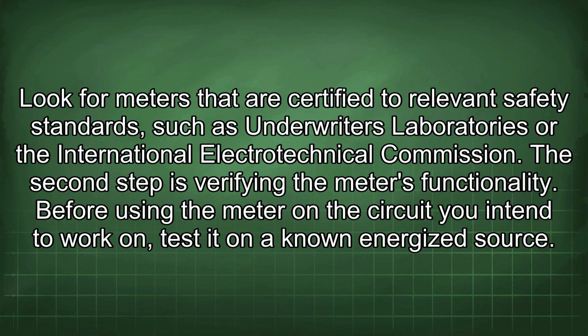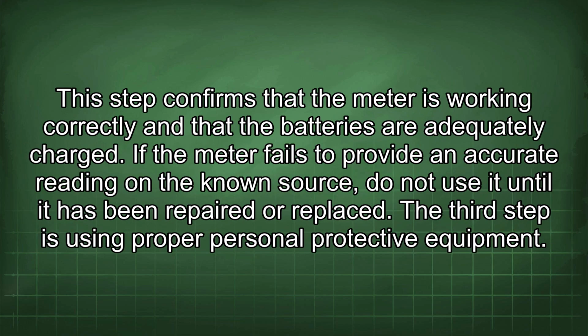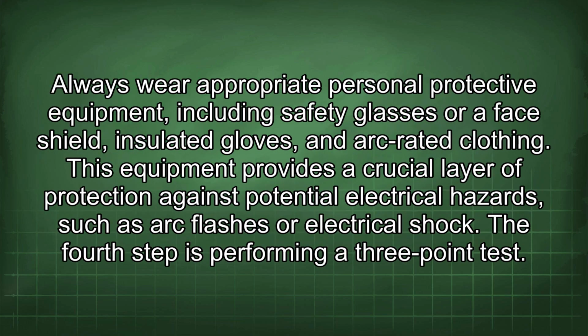The second step is verifying the meter's functionality. Before using the meter on the circuit you intend to work on, test it on a known energized source. This step confirms that the meter is working correctly and that the batteries are adequately charged. If the meter fails to provide an accurate reading on the known source, do not use it until it has been repaired or replaced. The third step is using proper personal protective equipment. Always wear appropriate personal protective equipment, including safety glasses or a face shield, insulated gloves, and arc-rated clothing. This equipment provides a crucial layer of protection against potential electrical hazards, such as arc flashes or electrical shock.